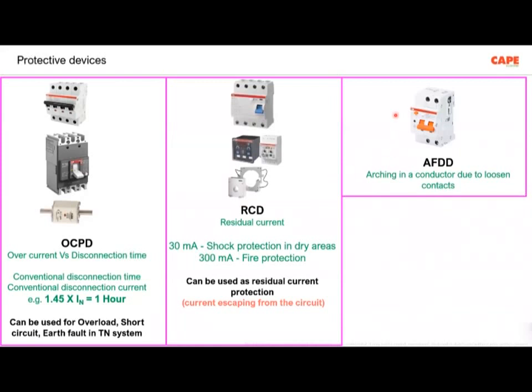The third kind of protective device is called AFDD, arc fault detection device. These devices are used to protect a circuit from loose contacts. Let us say you have a phase conductor with a loose contact; due to arcing, over a period of time it can ignite a fire. But the AFDD protects that particular circuit from arcs. So arcing in a conductor due to loosened contacts can be handled with an AFDD, but don't think that arcing at a loose contact in an earth wire will cause tripping, because the earthing is not considered here. Only the line and neutral in the case of a single phase circuit. If there is a loose contact, this device will trip.